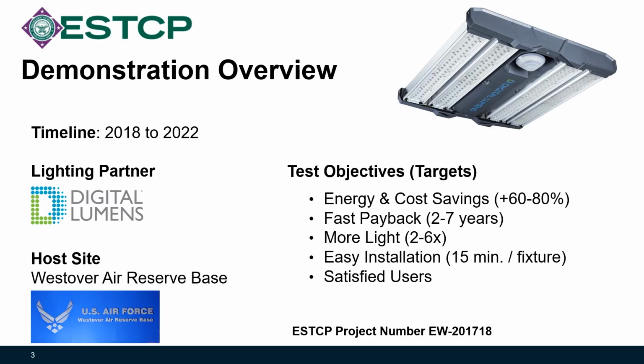The content for this presentation is based on an in-depth demonstration of a connected lighting system by Digital Lumens. Digital Lumens is a manufacturer of an advanced, fully integrated lighting control system. The demonstration was hosted at Westover Air Reserve Base in Chicopee, Massachusetts, and our test demonstrations were to show how advanced connected lighting systems can provide deep and cost-effective energy savings in common DoD facilities. In particular, we were targeting 60 to 80% energy savings with a fast payback, better illumination, easy installation, and high user satisfaction. A detailed technical report is in development and should be available on the ESTCP website sometime in 2023.